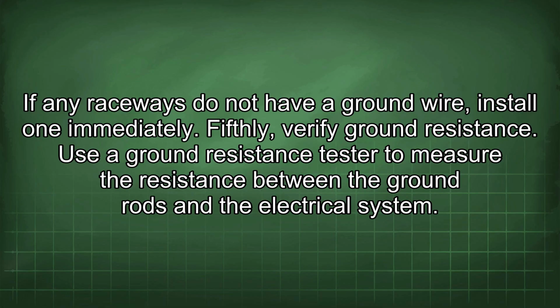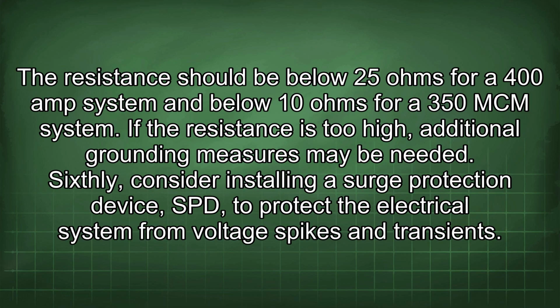Fifthly, verify ground resistance. Use a ground resistance tester to measure the resistance between the ground rods and the electrical system. The resistance should be below 25 ohms for a 400 amp system and below 10 ohms for a 350 MCM system. If the resistance is too high, additional grounding measures may be needed.